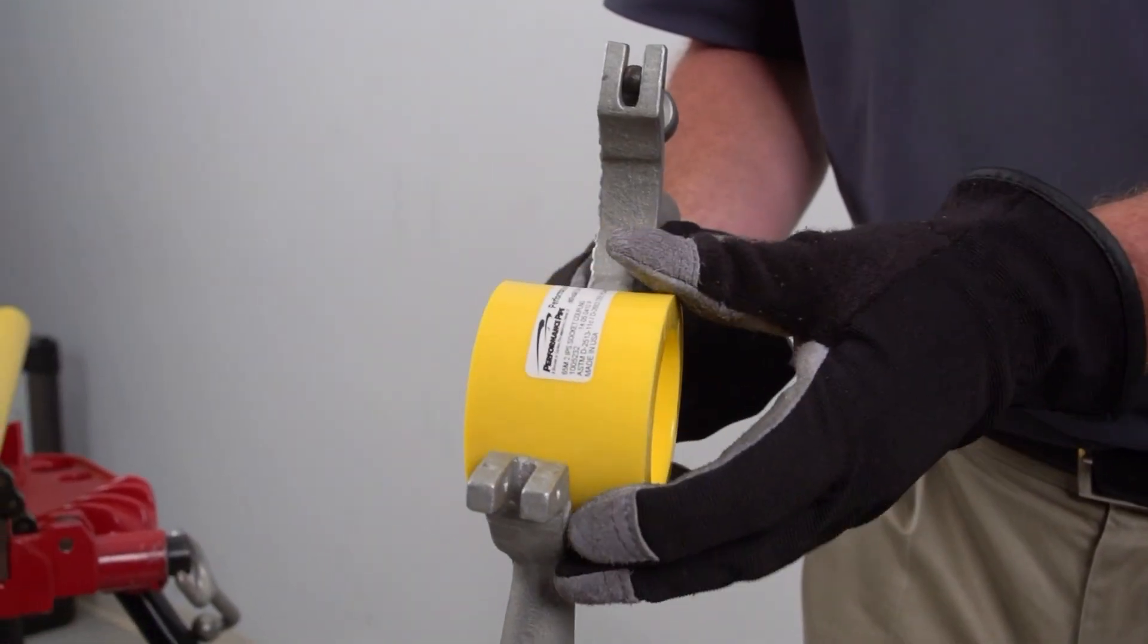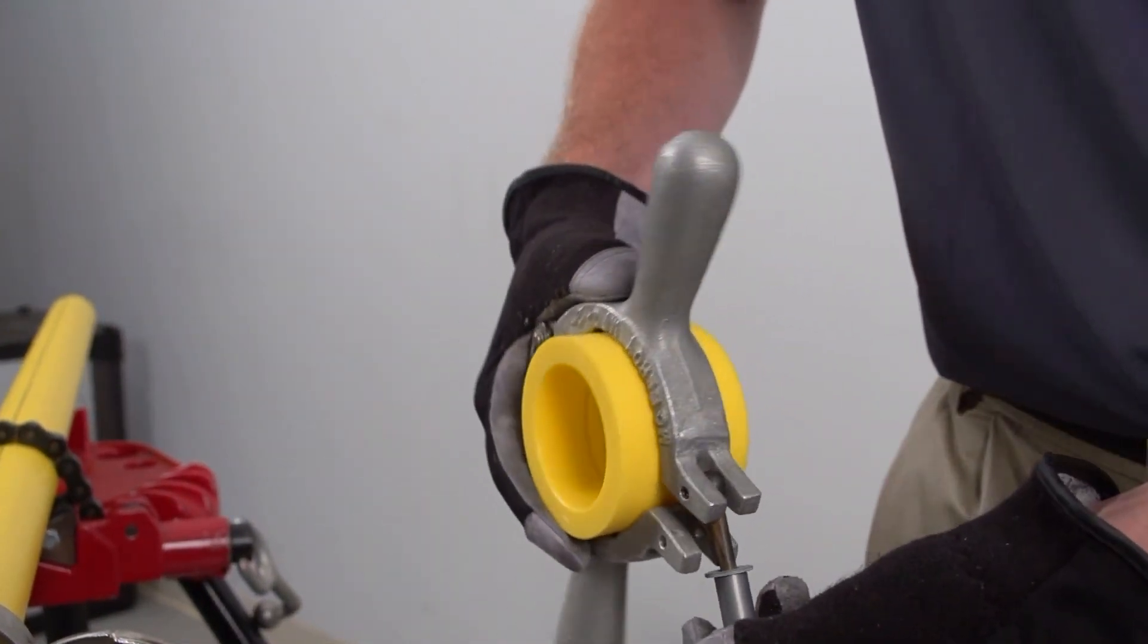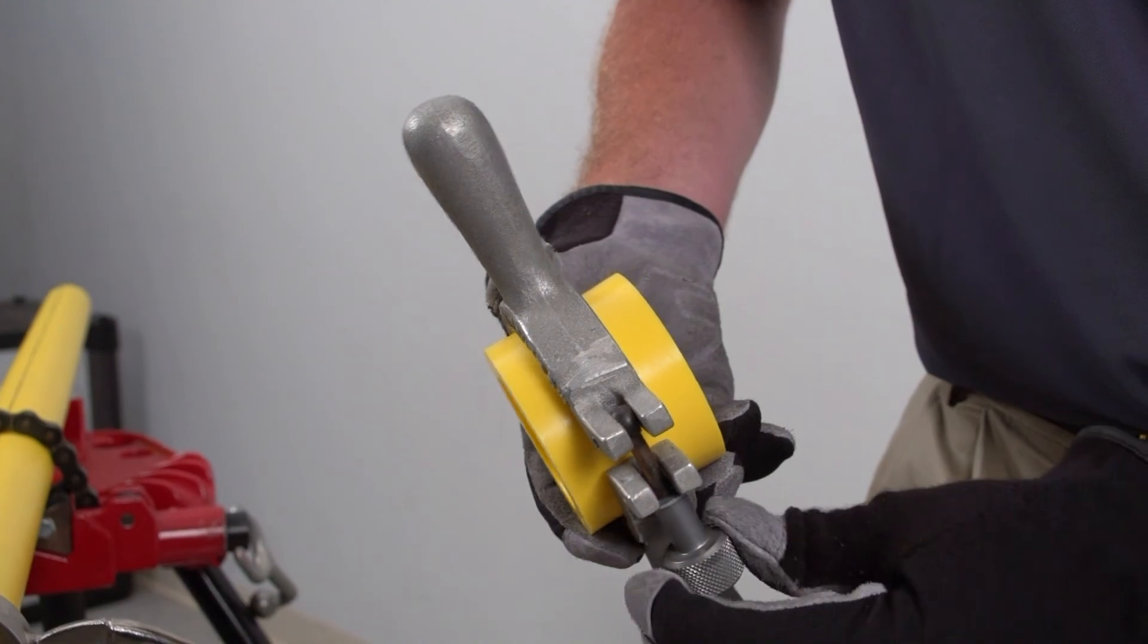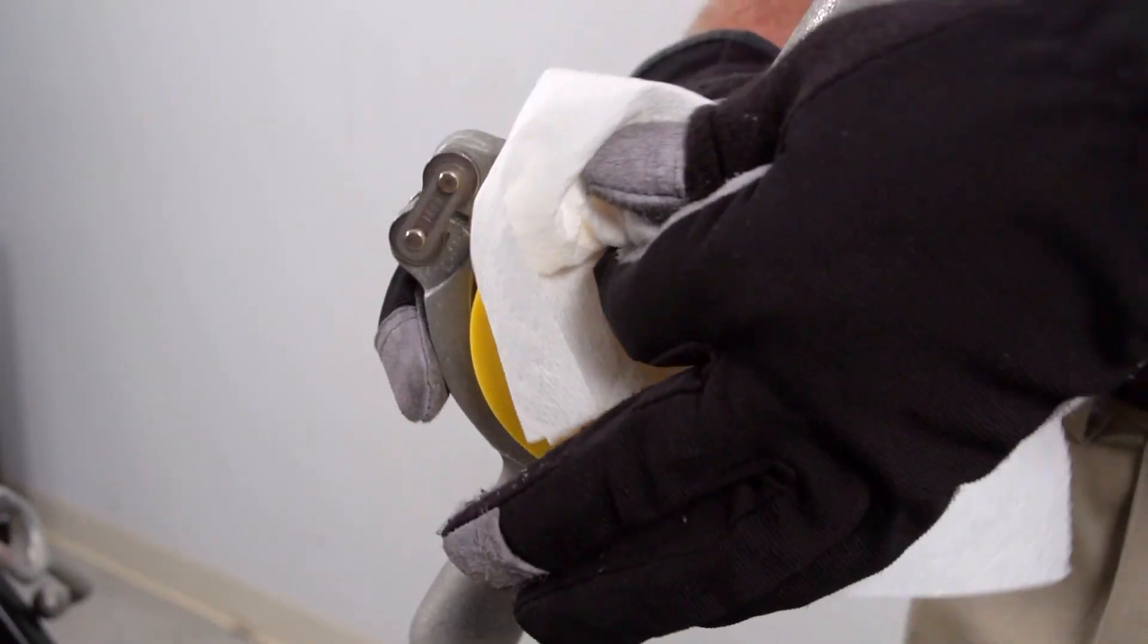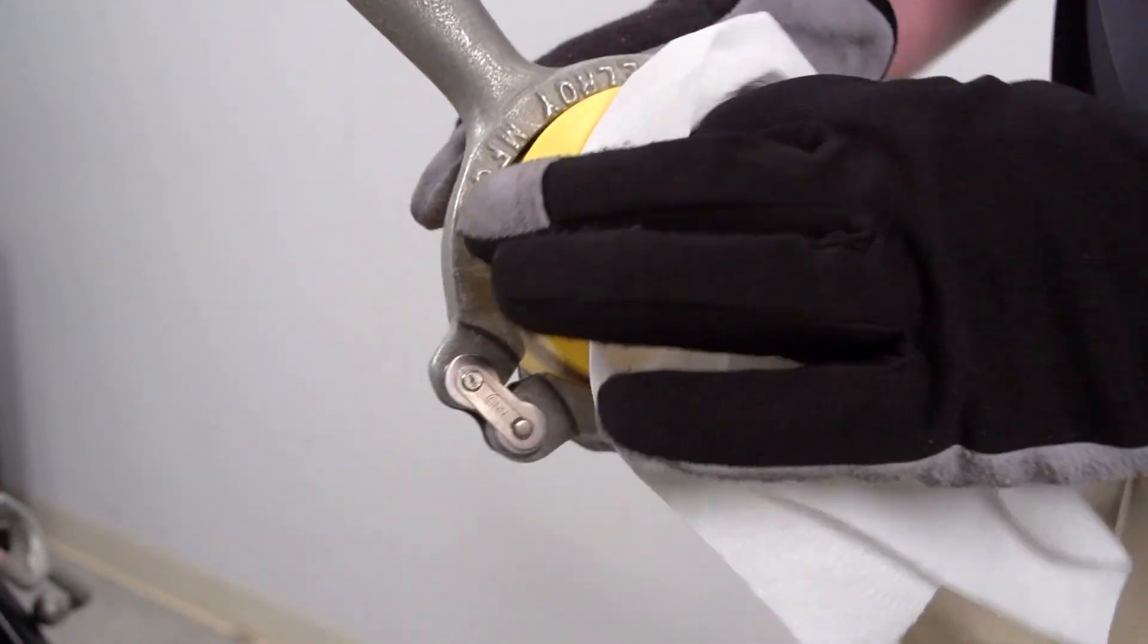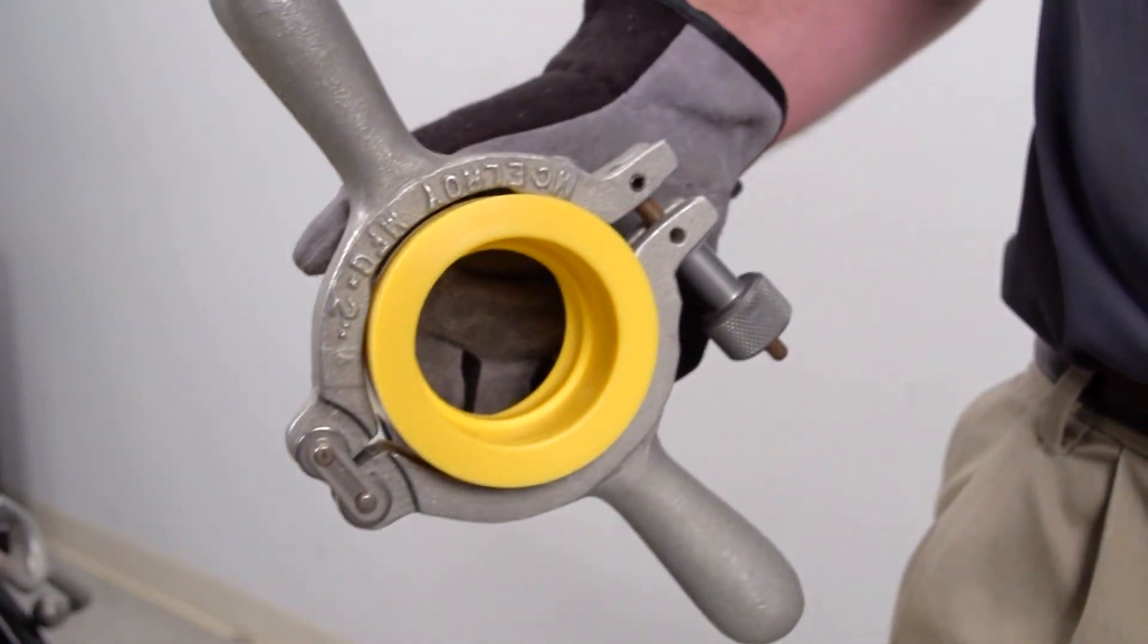Install the fitting holder if used and wipe the fitting socket with a clean, dry, lint-free cotton cloth or paper towel. Do not touch clean surfaces with your hands. Refer to ASTM F2620 or Performance Pipe Bulletin 750 for the recommended heating and cooling times for the correct pipe size.